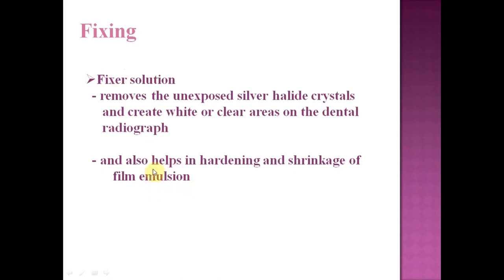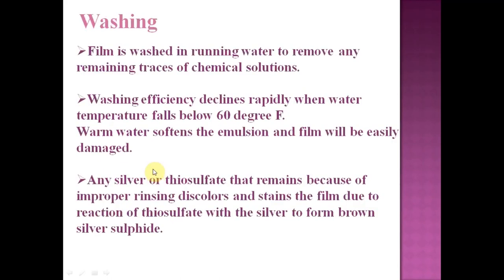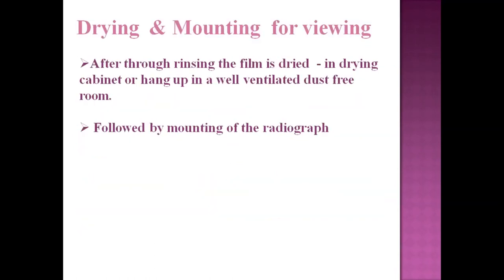The film is then washed in running water to remove any remaining traces of chemical solution. Washing efficiency declines rapidly when water temperature falls below 60 degrees. Warm water softens the emulsion and the film will be easily damaged. Any silver thiosulfate remaining due to improper washing will result in discoloration and staining of the film. After that, the film is put out for drying and mounting for viewing.